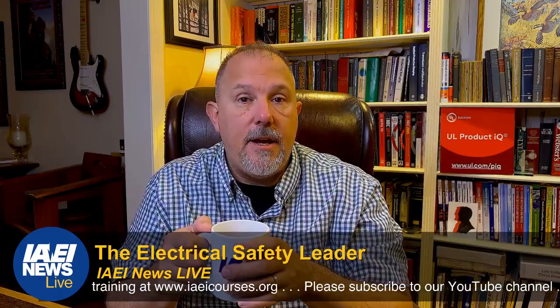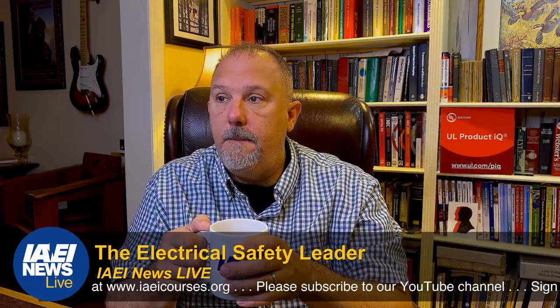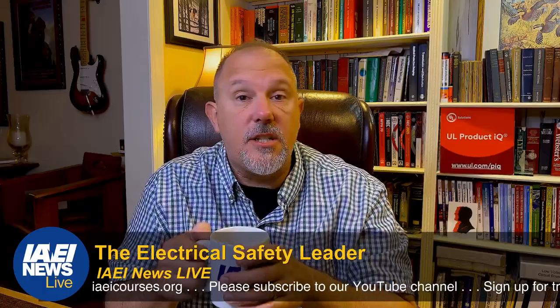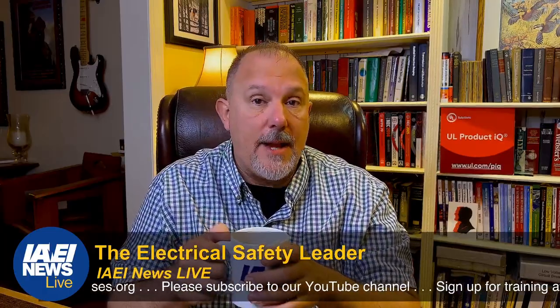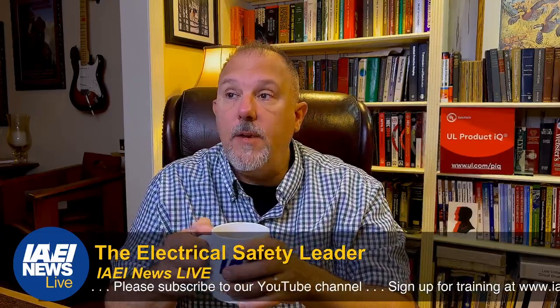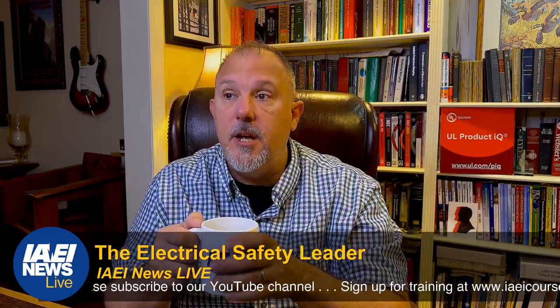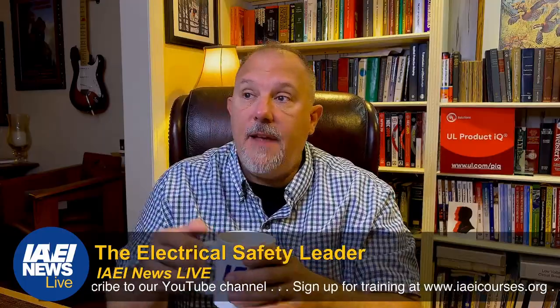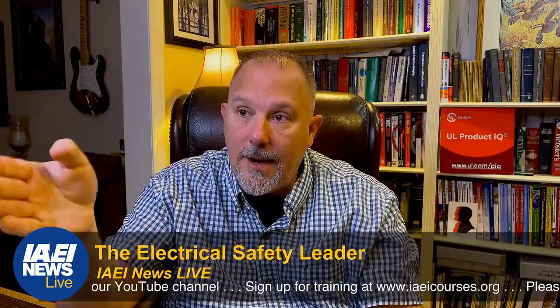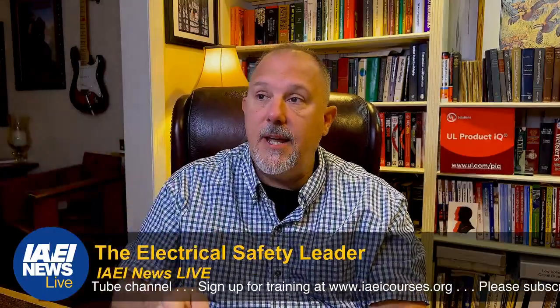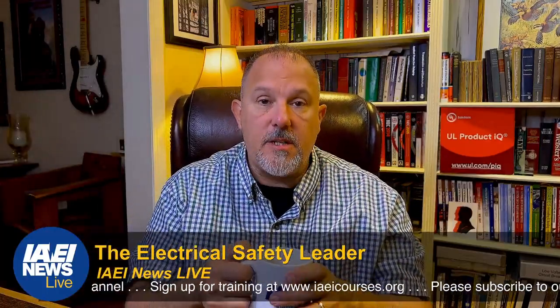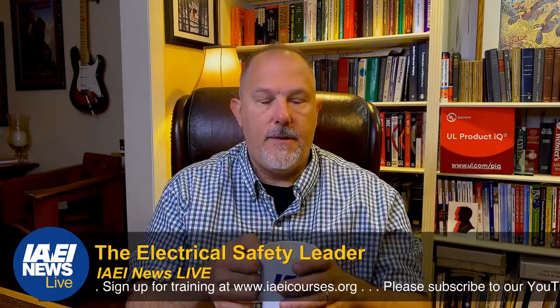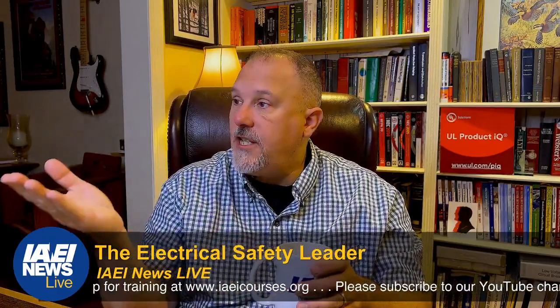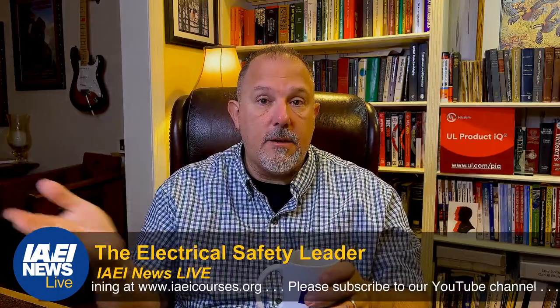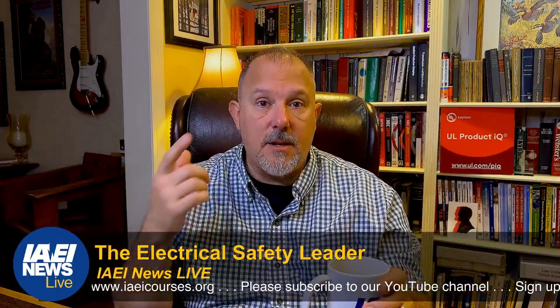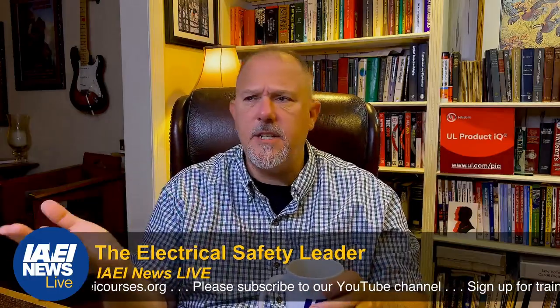So if I have a premises security system, there's the language we added in '23: receptacles supplying only a permanently installed premises security system shall not be considered as meeting these requirements. And if you have a receptacle required for specific equipment, and I would say possibly a premises security system, but if you have any piece of equipment like the HVAC under 422, where it said the air conditioning unit, the central air, has to be on its individual branch circuit—well, that's an individual branch circuit.